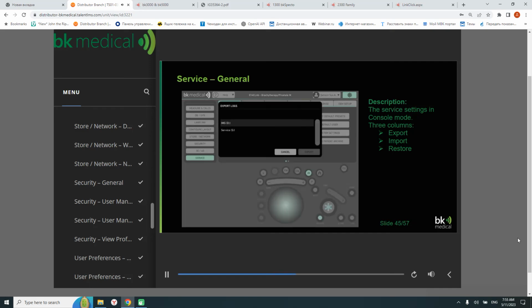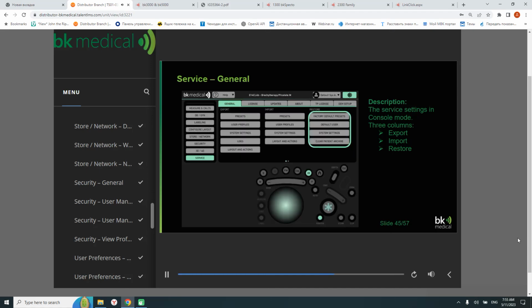Insert a USB flash key and select the drive on the list and press Export. Wait for the files to be transferred. The last column is for Restore. Clear patient data is password protected. The password is the password of the default system administrator. It is important to notice that when patient data has been deleted, it is not possible to recreate it.